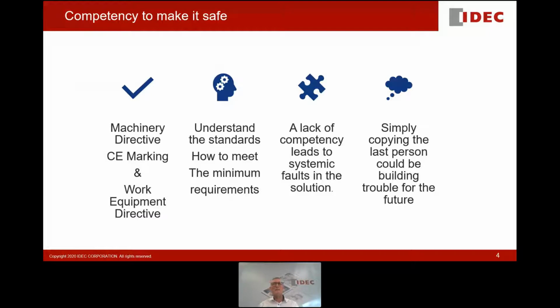But what if we were to change a device that creates the same functionality, so the device actually does the same thing, but do we know whether or not it's actually delivering the same level of integrity? We probably don't. So for that reason, later in the presentation, I'll talk to you about the effects of making changes that do change and literally make the safety function different, though the machine function remains the same.